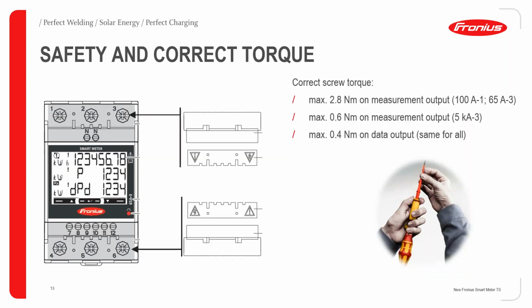Because many times, even when it comes to the inverter or the smart meter, we don't pay close attention to the torque values, but it is very, very important. Maybe you get it right 1 or 2 times when you try, even if there is an error. But to get it right the first time itself, you have to pay close attention to everything. For example, these torque values. So the maximum torque you can apply to the output side, output cables, is 2.8 Newton meter.